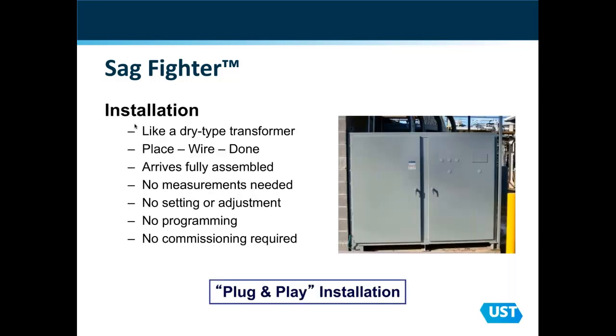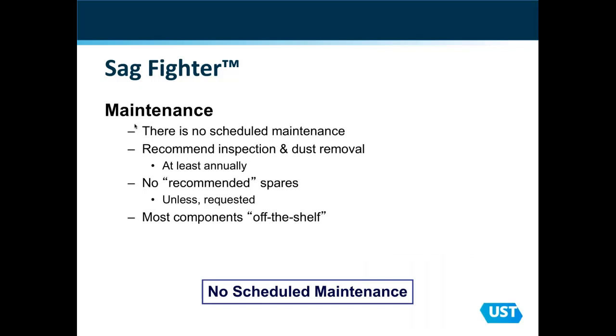Installation, I mentioned this, very easy to install. It installs pretty much like a dry type transformer. We do provide an input circuit breaker on the device, so your input connections all go to the input circuit breaker, and then we provide a set of output lugs for your load. Again, I mentioned maintenance, very simple.